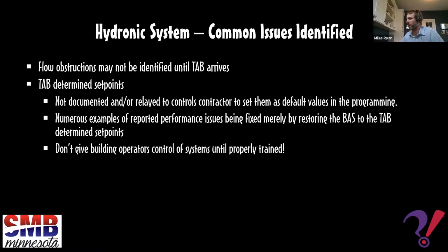When we looked at the system, we said, well, geez, it looks like the serving air handling unit is actively trying to dehumidify. The cooling valve is open completely, but we're not really seeing a big temperature drop in the air at the air handling unit. We're also not seeing the chilled water pumps speed up much. So we started asking the question, what's the appropriate set point for the chilled water pumps? We asked the contractor who installed the new control system, and they said, we're just using this value.